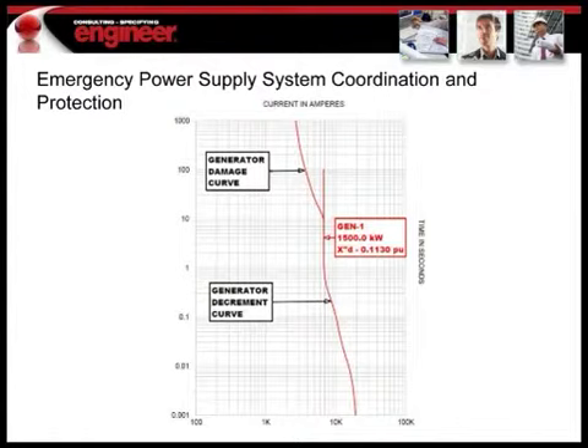And you can see what it does is it decays, and then at a certain point it would reach 300% of the full load current, which would be your PMG kicking in and allowing that additional fault current to be on the system. And at some point, typically somewhere around 10 seconds, it'll intersect with the damage curve. And then the damage curve goes up, and that's a model of the curve that we had already just shown based upon per unit values.